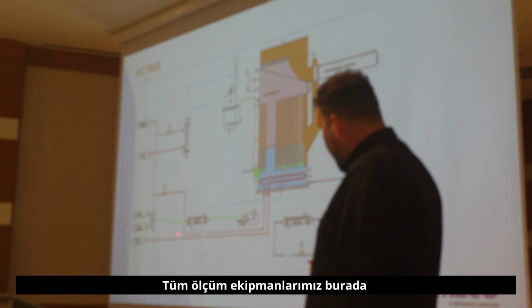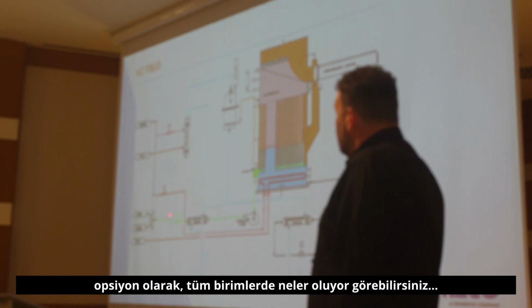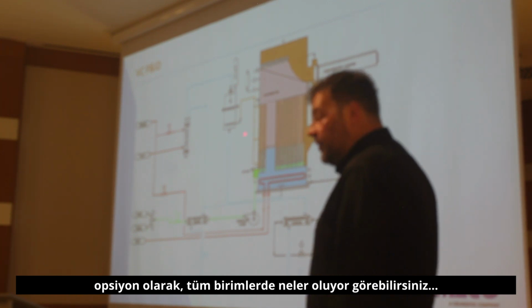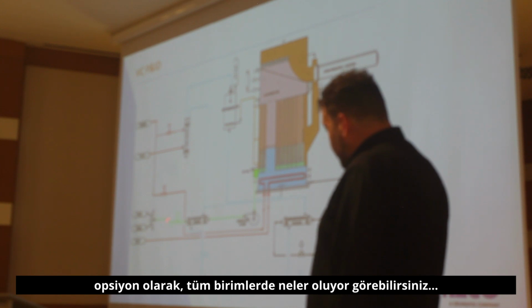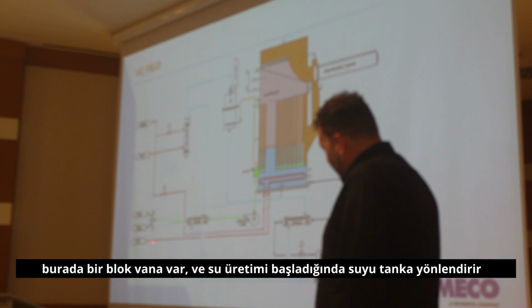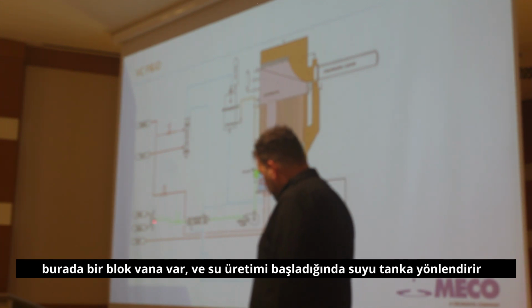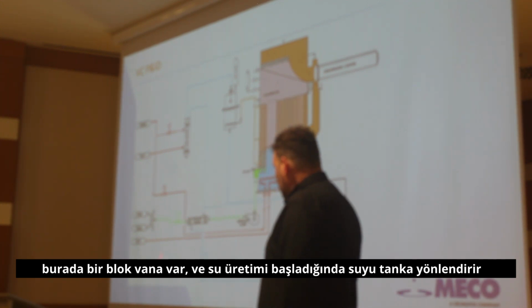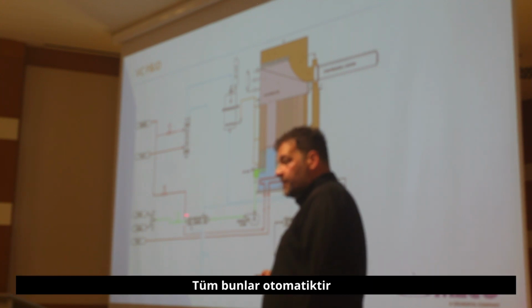All our monitoring is here, as we know from any purified water technology. TOC if you want, that's an option. Conductivity, everything is measured here, and there's a block valve at the end. If the water's good, it goes to storage tank. If it's bad, it will be diverted. So that's all automated.